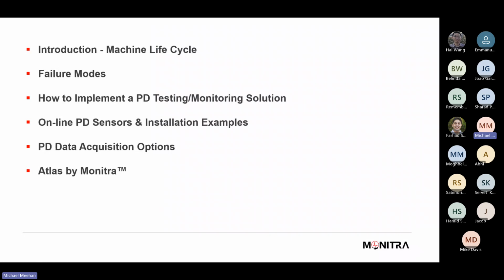So today some of the key points are machines. What are their criticalities and what's the typical lifespan of a machine, and what might be some of the challenges in maintaining a machine in optimal life over the course of the needed operating requirements of asset owners, especially in this current day and age where we've got assets which are 20, 30 plus years of age and expected to run another 20, 30 plus years. So we need to be looking at how those assets can be kept in service for the foreseeable future, as well as new assets coming online, what can be adopted as best practice to help maintain those assets. And PD testing, which we'll get into, is one method of ensuring that a machine is in its optimal condition for long service life.